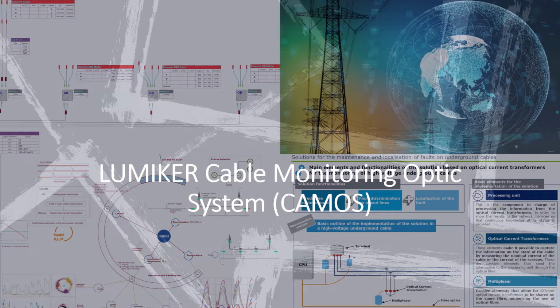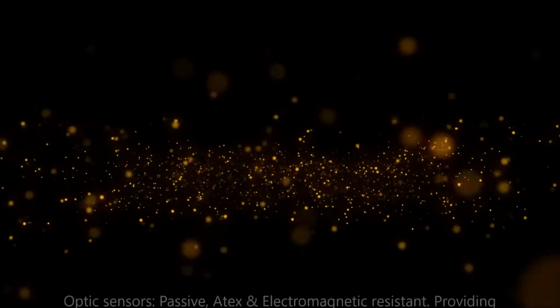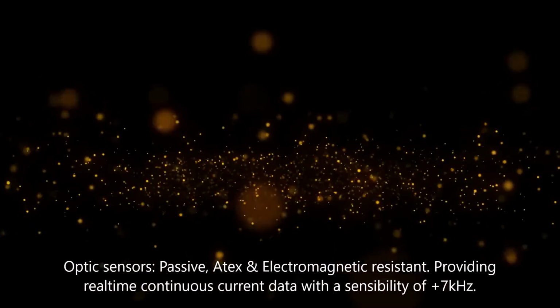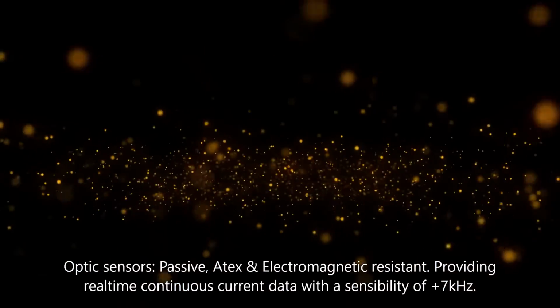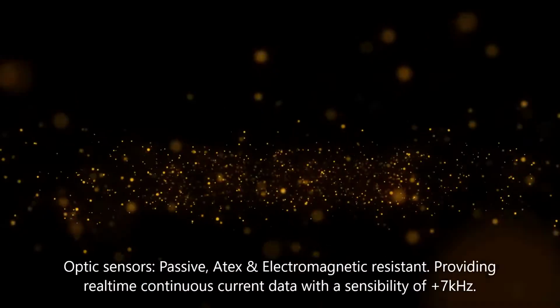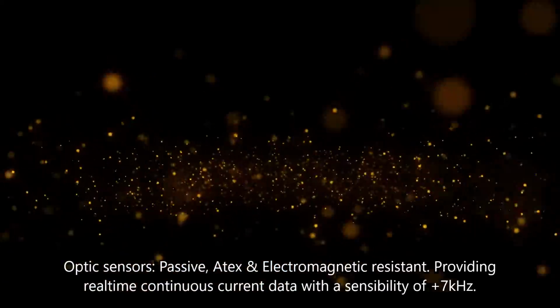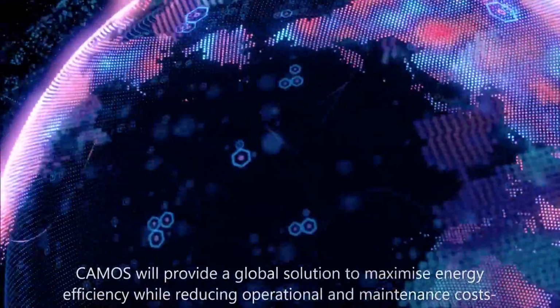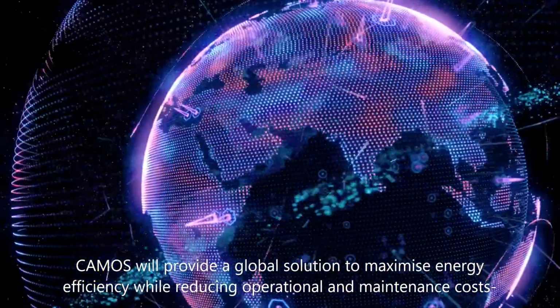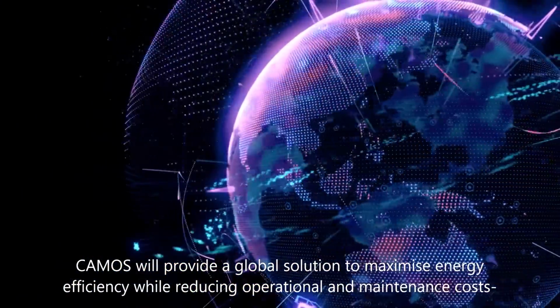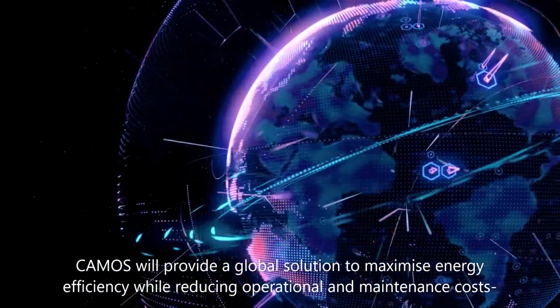Our system consists of three elements: a processing unit that processes the signals received from the optical current transformers and converts them into data connected to the client; the OCTs that capture information from the cable and send it to the CPU through the optic fiber; and multiplex systems that allow different OCTs to share signals through the same fiber, minimizing the use of normal optic fiber.